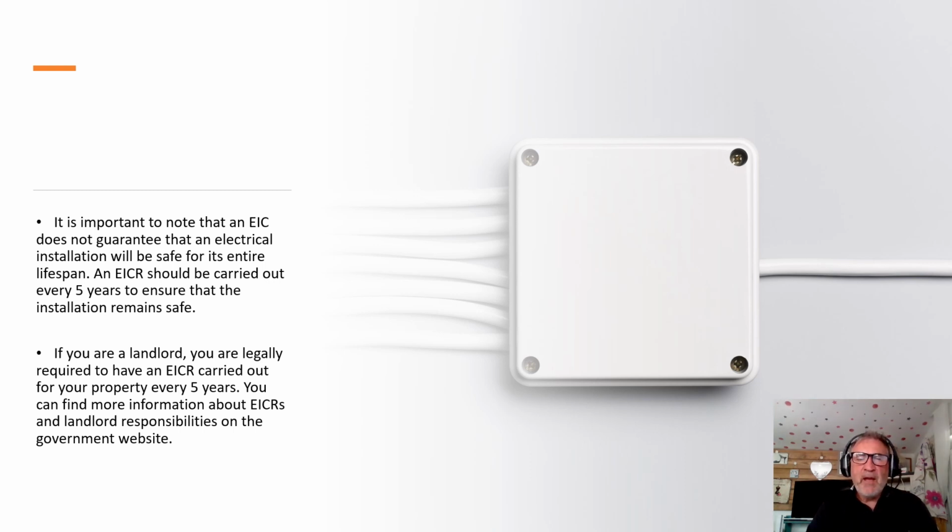If you're asked about the frequency of testing, there's a lot of variables in there. It depends what the premises are and what they're used for. But on an electrical installation certificate, when we actually complete them, we'll be completing a section where you, as the tester, will recommend a frequency of next inspection. Now, if it's a new circuit, it's reasonable, you can put down 10 years.